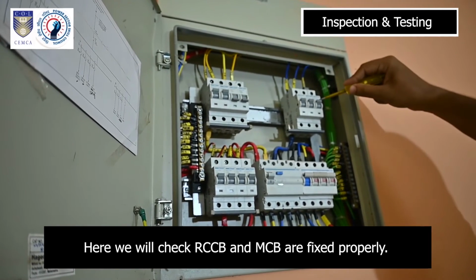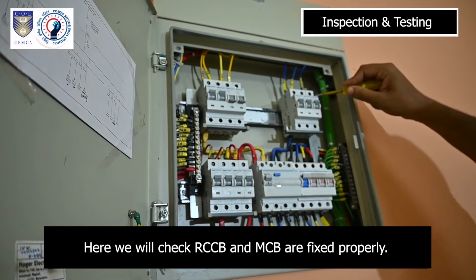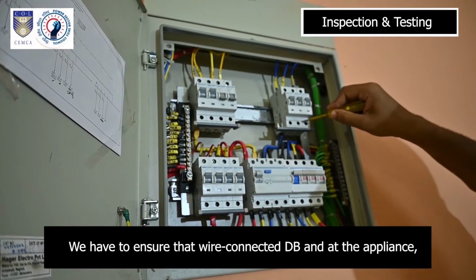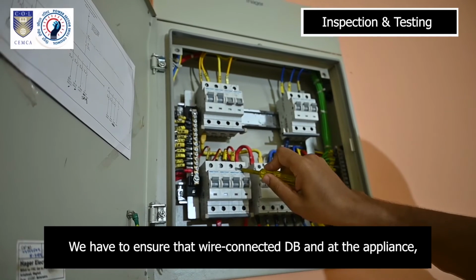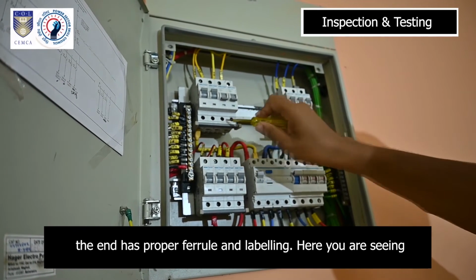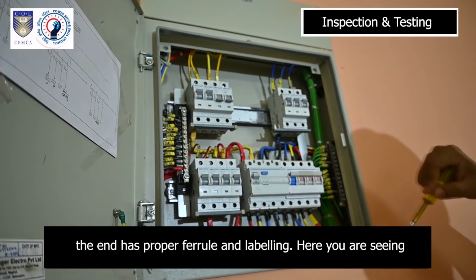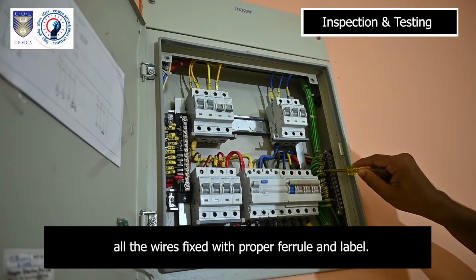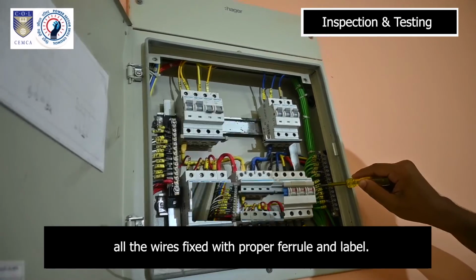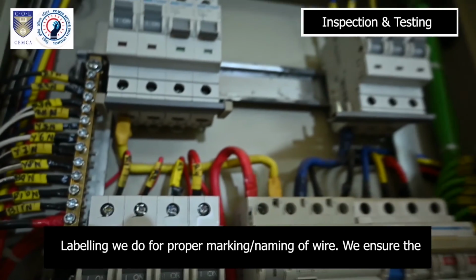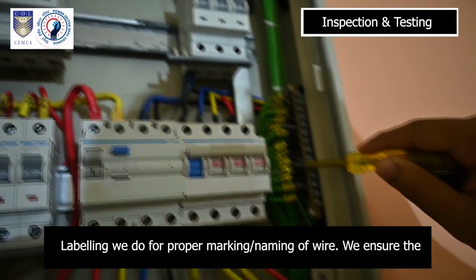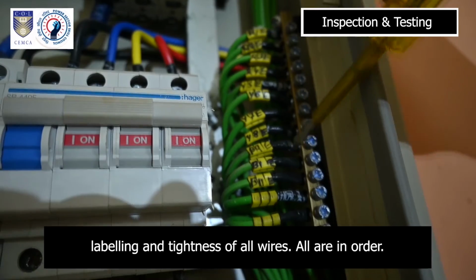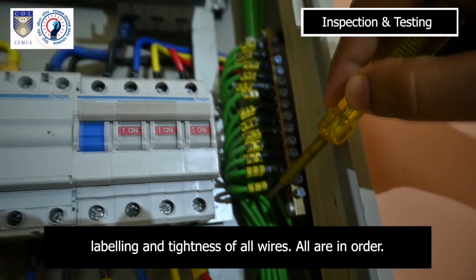Here we will check that the RCCB and MCB are fixed properly. We have to ensure that the wires connected at the DB and at the appliance end have proper ferrules and labeling. Here you are seeing all the wires fixed with proper ferrules and labels. Labeling is done for proper marking or naming of wires. The labeling and tightness of all wires are in order.